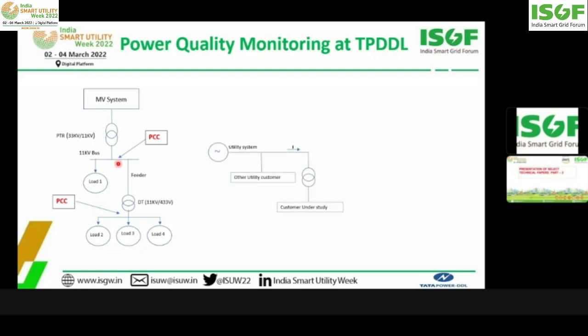Now here's the case of industrial customer. Here, if an industrial customer is being supplied through a dedicated service transformer, and we are interested to take power quality measurements, then the PCC point for us would be HT of this dedicated service transformer from where utility can supply to other customers also. And if you are interested in measuring power quality at commercial systems, which are being served through a service transformer, and from LT of that service transformer, other utility customers are also being supplied, then in that case, PCC would be LT of this transformer.